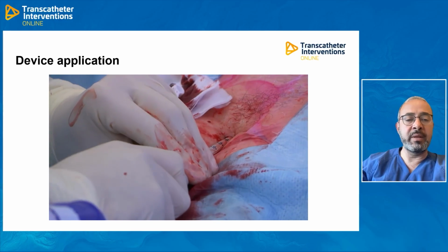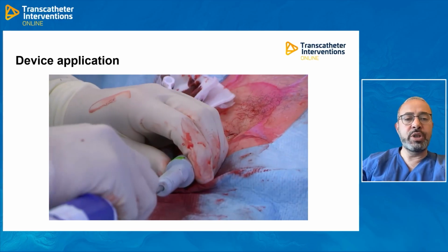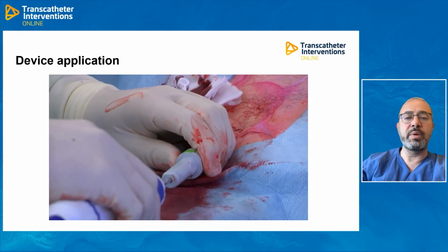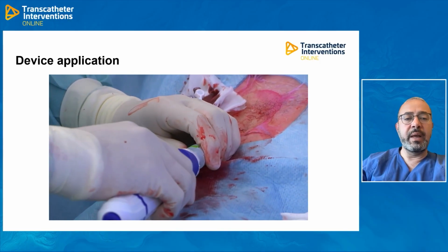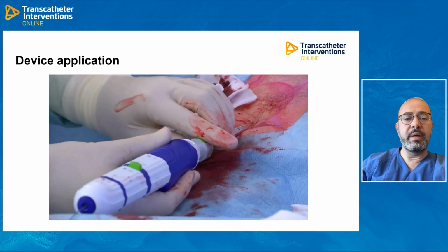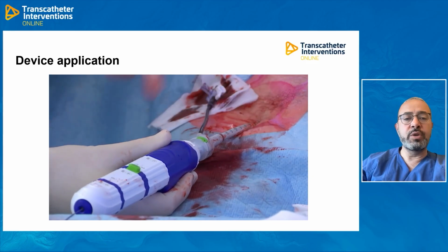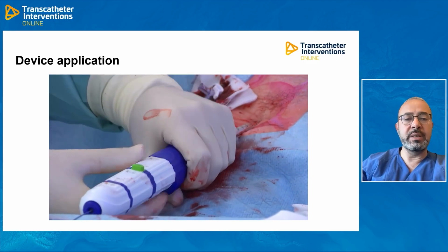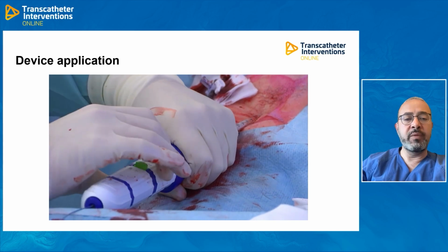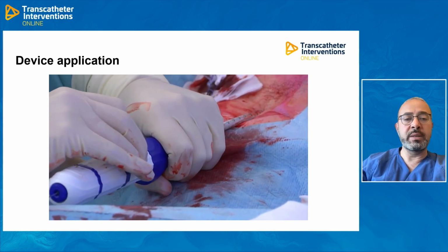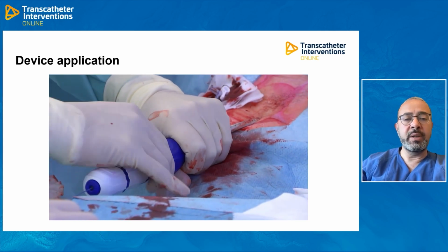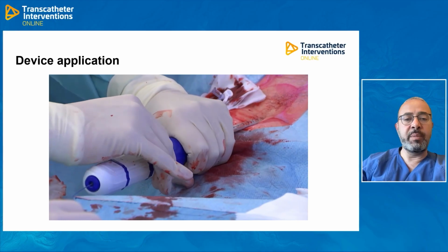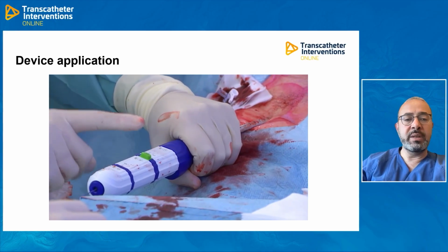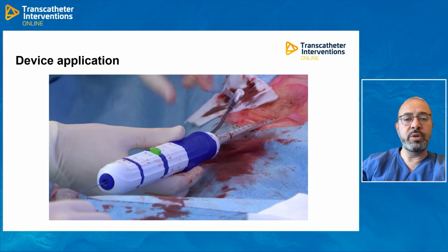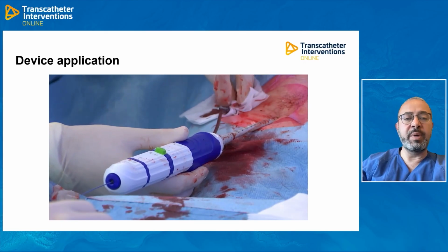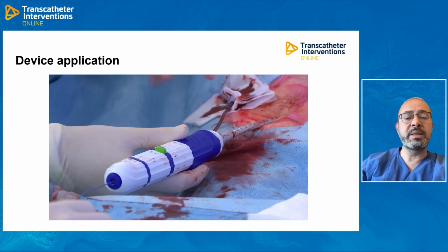After that, the wire remains in place, and you introduce the patch-holding delivery catheter, just pushing it into the sheath, holding the sheath in place, and then after that, you start exposing the patch inside the vessel by rotating the first knob clockwise. So you'll see now that the operator with his left-hand side is stabilizing the system, and with the right-hand side, rotating the knob in order to get the sheath a little bit backwards, exposing the patch.